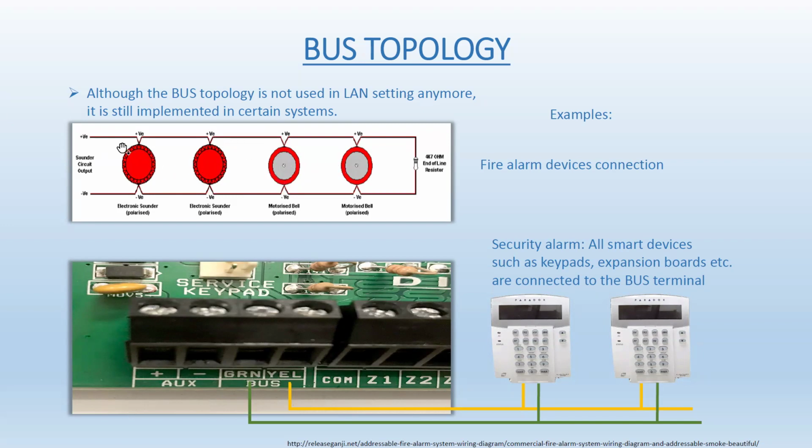What the zone needs to see in the fire alarm, because if those are open, you can just imagine they don't exist, because the zone doesn't see them until the switch in each individual one closes if it detects what it is supposed to detect: fire, well, smoke, fire, heat. All right. So if those are open, they don't exist, sort of.